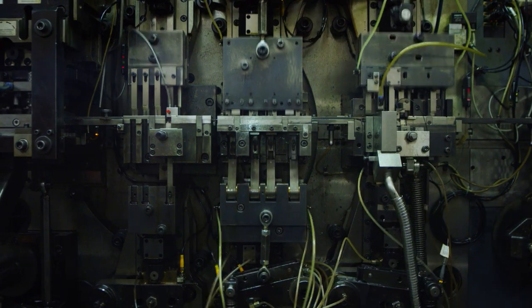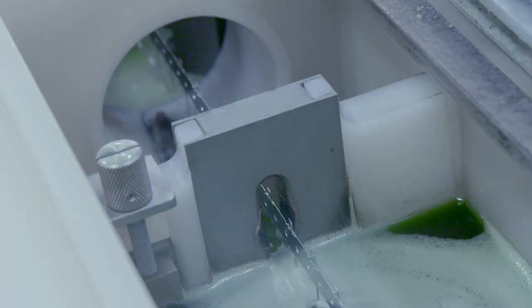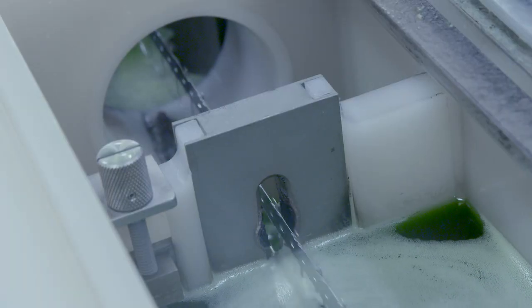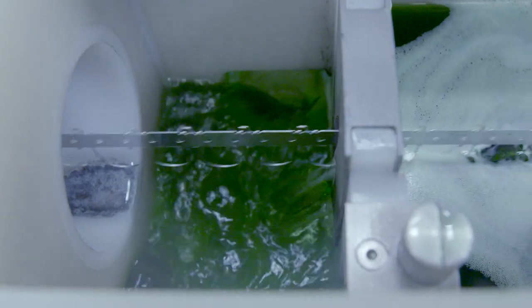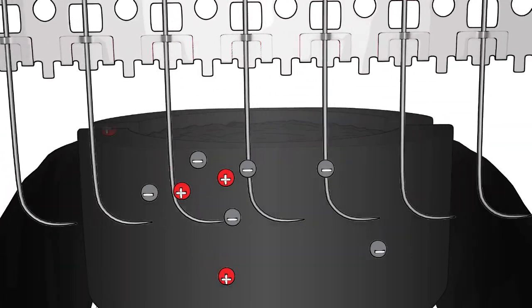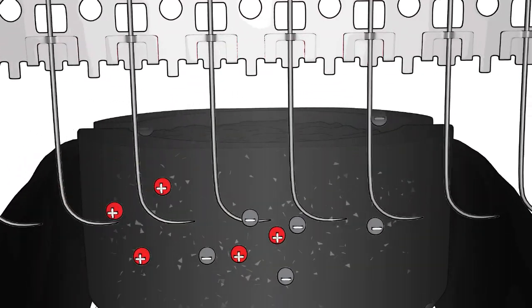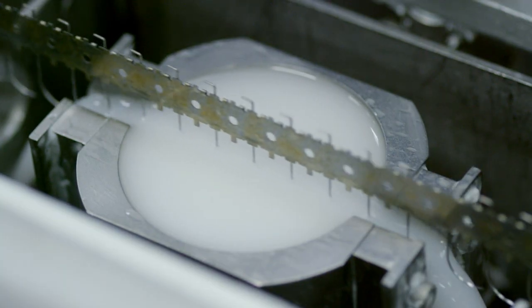Needles that get to the point are curved and rolled and sent for electro polishing, which strips unwanted material from the needle by dipping them in acid then adding electricity. The needles are then treated to a lubricious coating for easy, smooth passage through tissue.